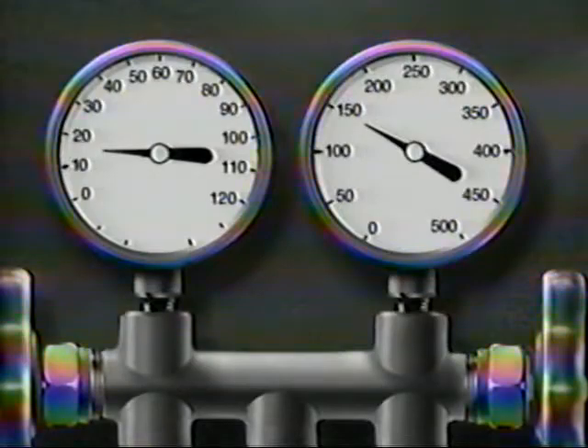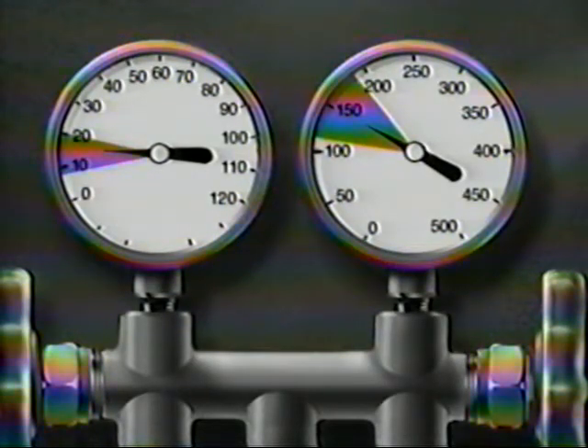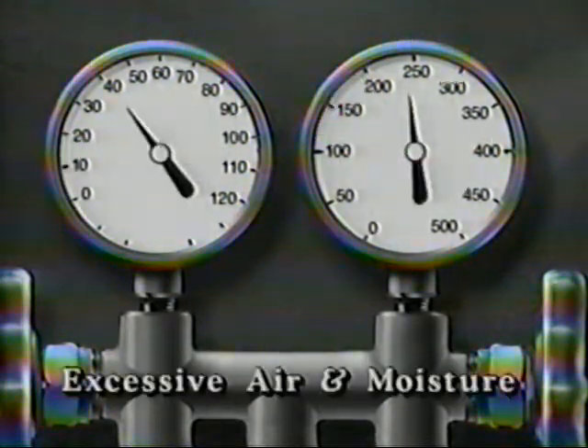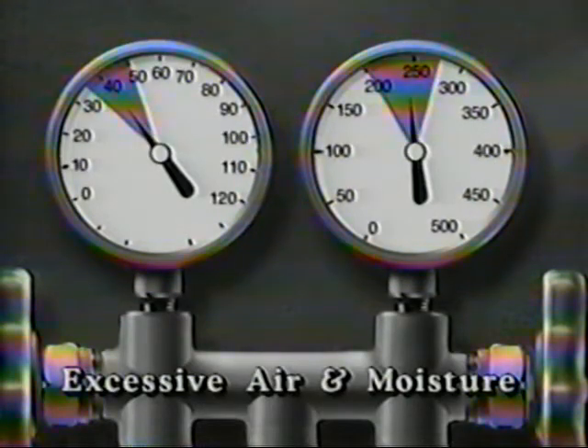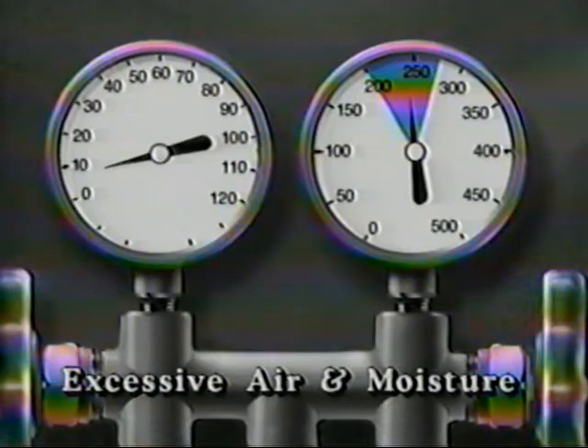If there is some air and moisture in the system, pressure readings will be normal even though the air conditioning is providing insufficient cooling. Any leaks will have to be repaired. If there is excessive air and moisture in the system, the suction pressure will be high at first, then drop to a lower range, or indicate a vacuum as the system runs. The discharge pressure will run high. Any leaks will have to be repaired, and the system will require purging or flushing.